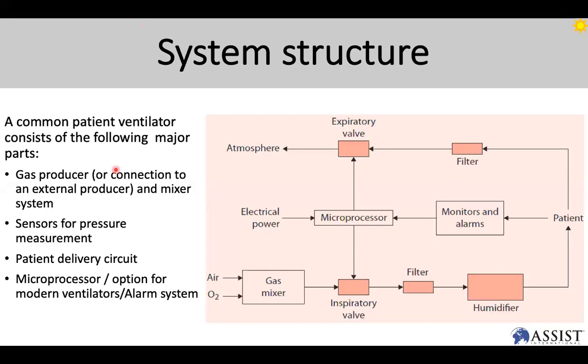Got it. Okay. So as Gunnar was explaining, this is sort of the very basic block diagram of a ventilator. It can seem very complex on the outside, but as engineers, we've got to try and simplify this picture down. And so he mentioned some of the key components of a ventilator. You've got the air and oxygen coming in to what we call a gas mixer. Sometimes there's N2O as well involved. And then you've got the inspiratory and expiratory valves. You've got filters that are present, and then humidifiers. Ultimately, you've got patient delivery circuit. And all of this is driven with the help of microprocessors, monitors and alarm systems, and electrical power in the form of either direct power, line power, or you've got battery backup as well. There are also ventilators that just run on pressure alone, and so that's maybe something for a separate discussion at another time.